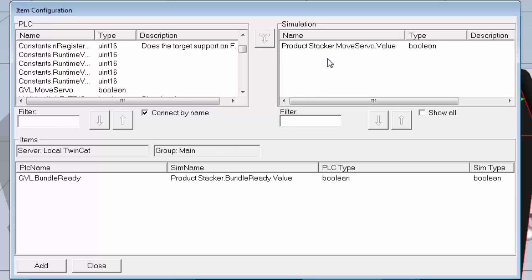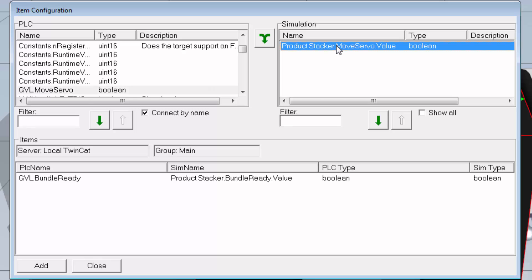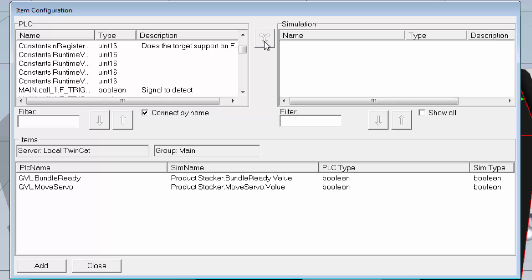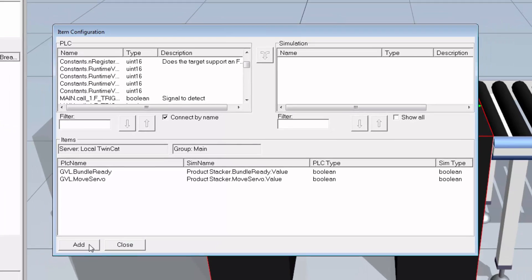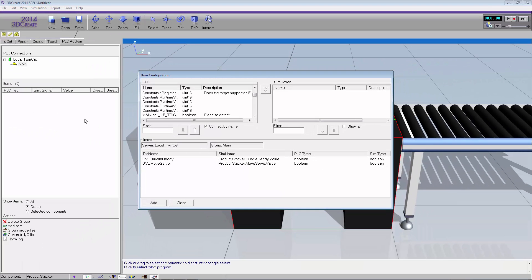I'll do the same for move_servo: select it, here's its PLC counterpart, click the converging arrow, and there they are. Sometimes you do need to turn off Connect by Name and manually map the signals, but in this case it's straightforward. The last and very important step: once your signals are listed and mapped, click the Add button so they're added to the PLC group — don't click Close, click Add.